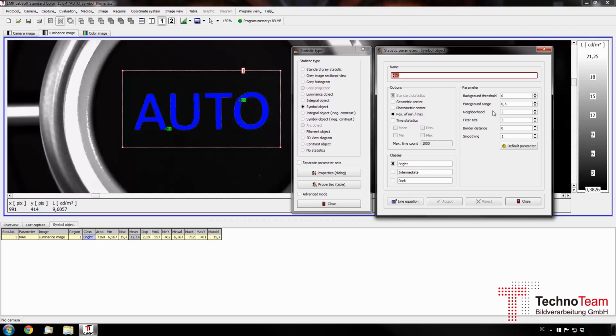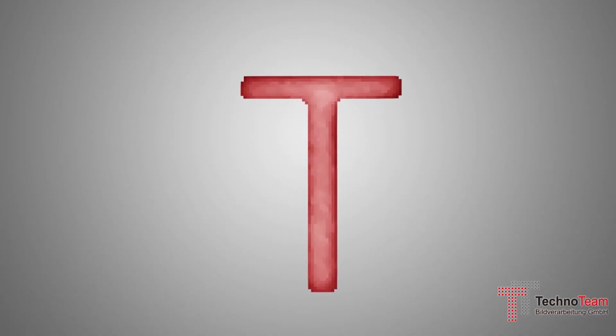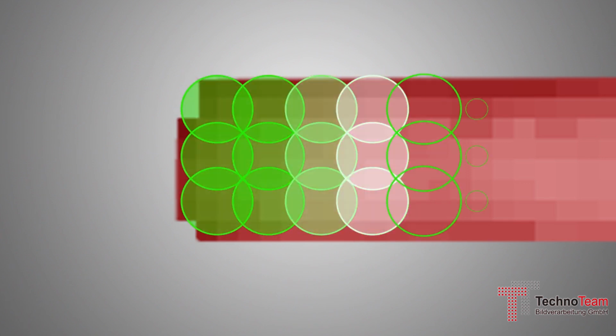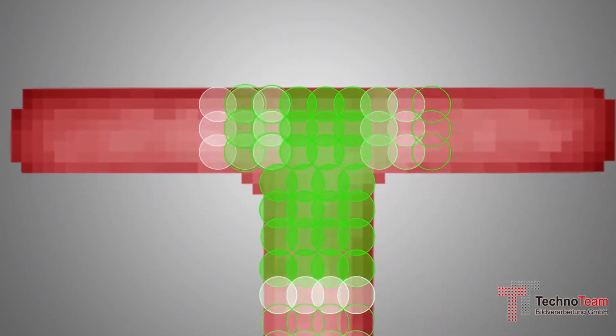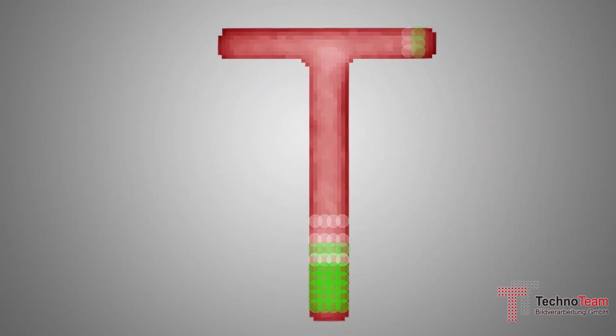With the help of the filter parameter, the size of the point sensor can be set according to the requirements. By default, the value of point sensor in the filter parameter is set to 3. It means that small circles of 3 pixel diameter spread across the image in the region. The minimum and maximum value of luminance in each pixel is analyzed by the software, and an average of the values of all the circles gives the minimum and maximum value of the entire region.